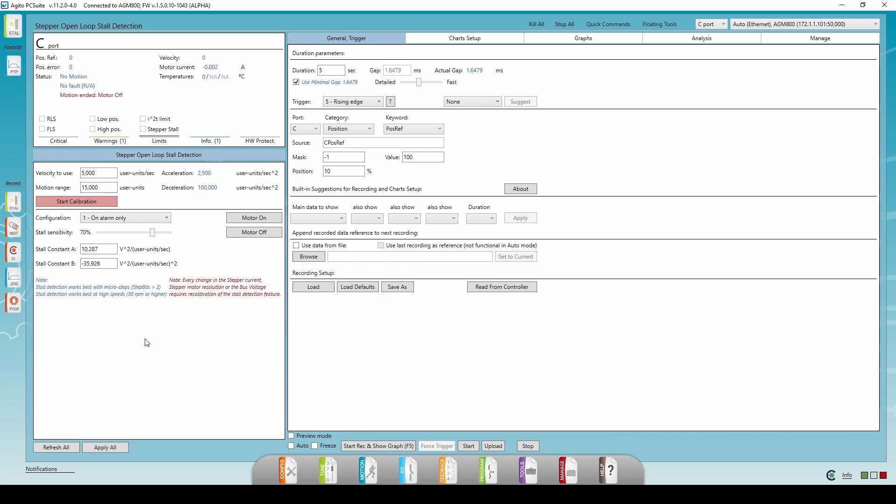Note that every change in the motor current configuration, the power supply to the motor, or the motor resolution requires recalibration of the feature. Otherwise, you may get false detections or missed detections.